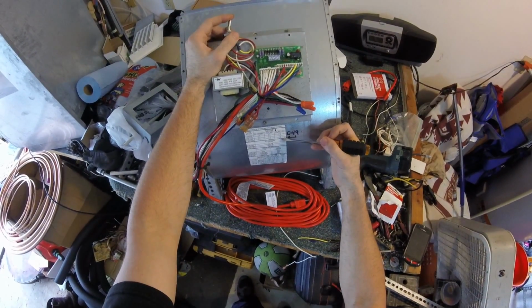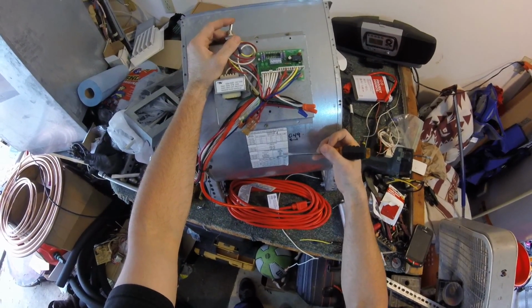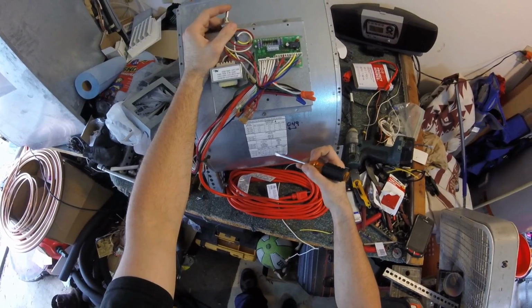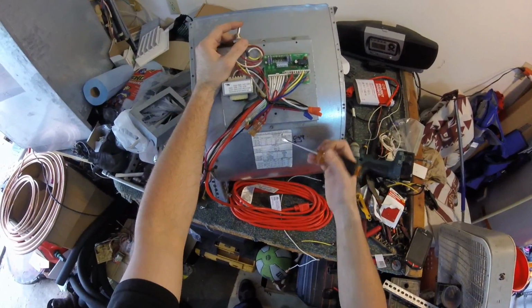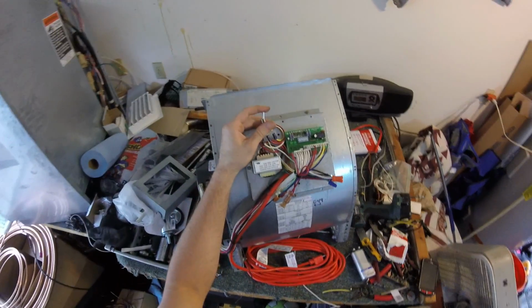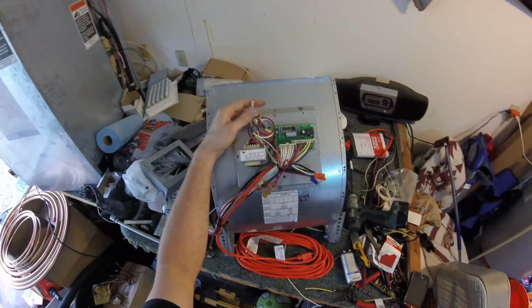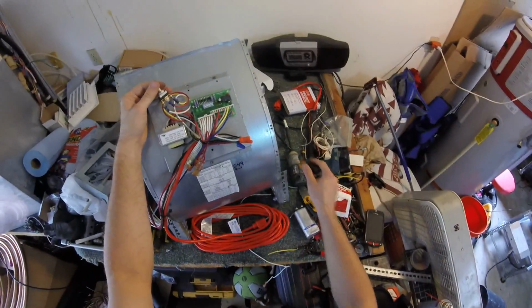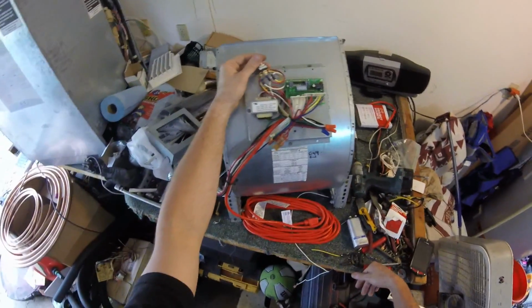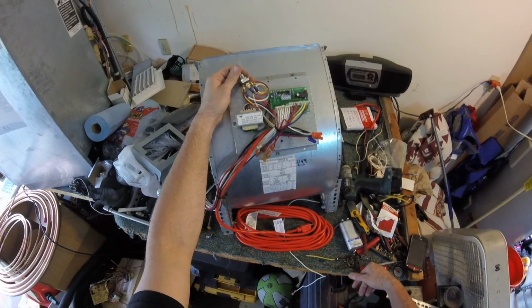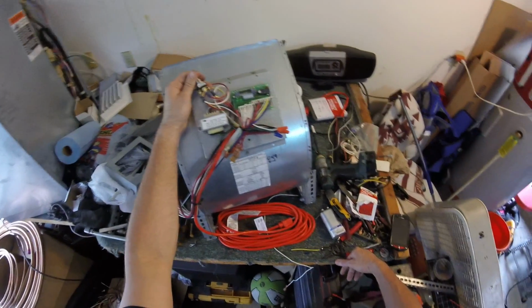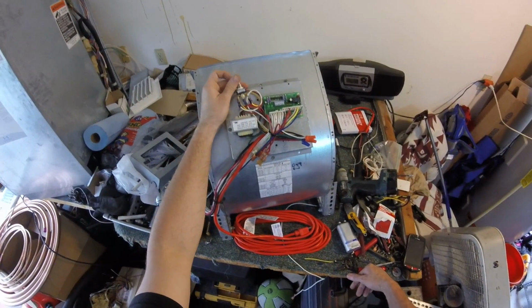You can go all the way up to 2000 CFMs, or you could do 1200. You've got your heat strip settings here, and then your G, your fan-only speed, which should usually be low. Nice and adjustable - you can set it up if you want more air or less air. You can change it real easy.